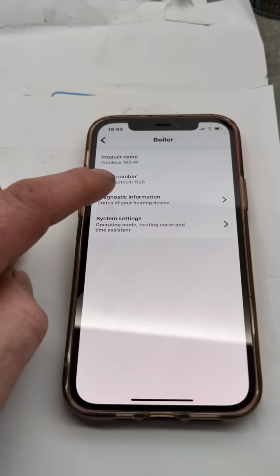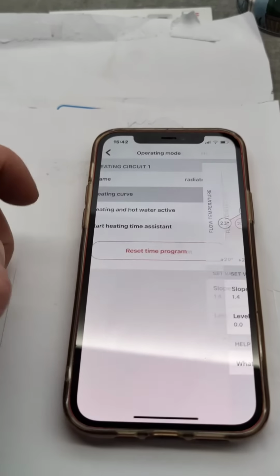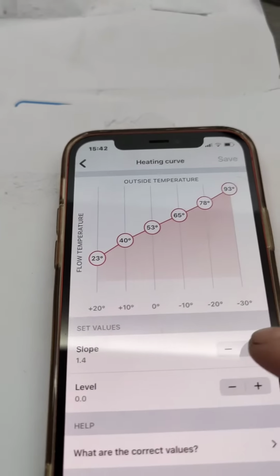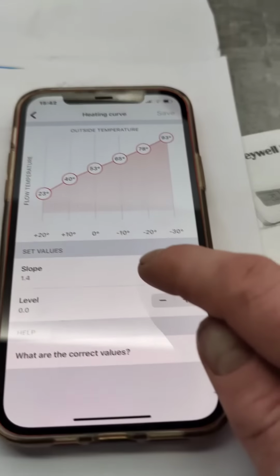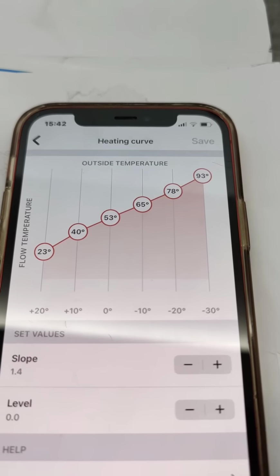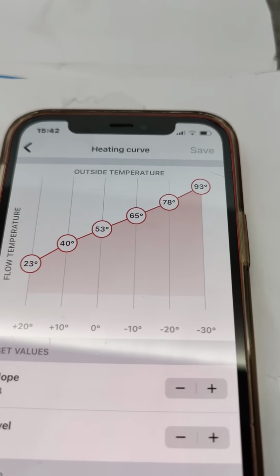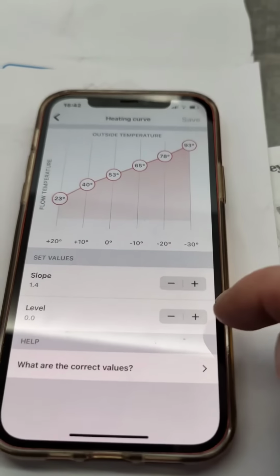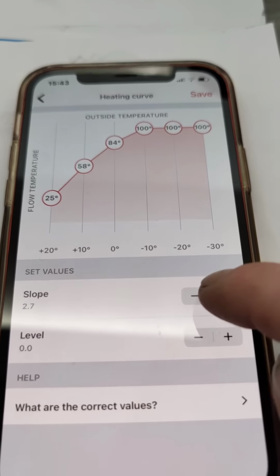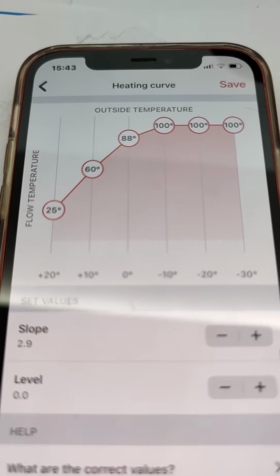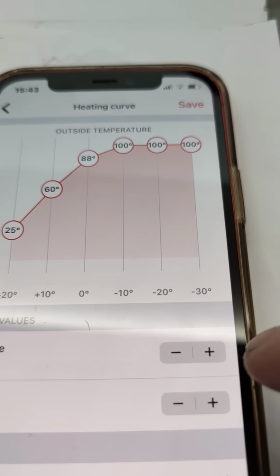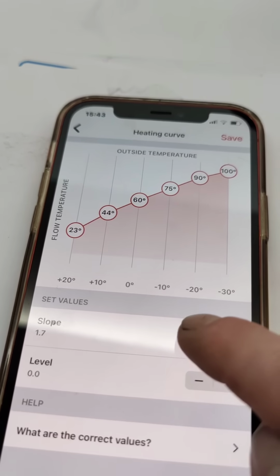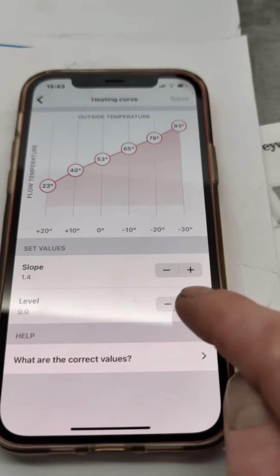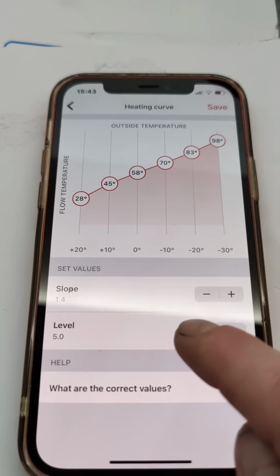So now we've got the weather comp connected, and we can go into the heating curve, and we can alter the heating curve up or down. So it's the standard set at 1.4, which means that when it's 10 degrees outside, the rads will be 40 degrees. When it's 0, the rads will be 53. When it's 20, it'll be 23. If the house isn't very well insulated, we can knock this up. So if it's 10 degrees, we'd have 60 degrees flow temperature, and we'd have maximum temperature as it gets into the minuses. So ideally, the lower we can set this, with the customer still being comfortable, the more efficient the boiler will be. Now we can also offset the level if we want the same curve.